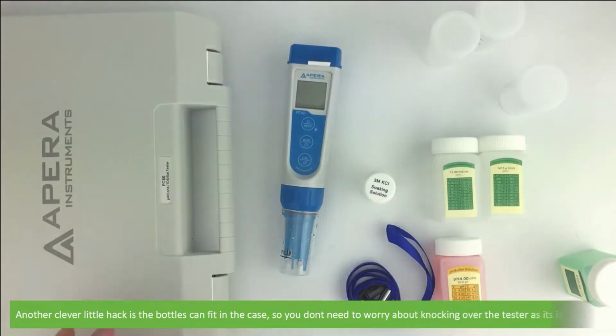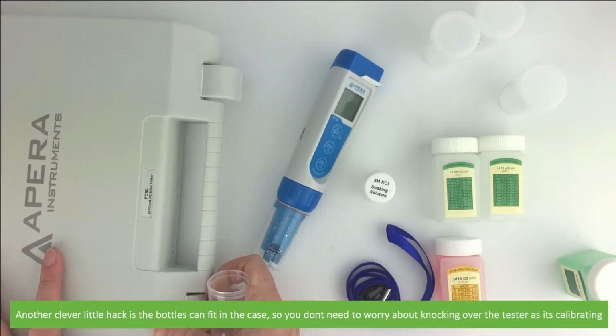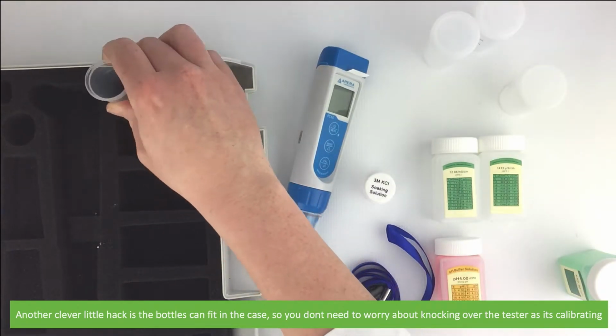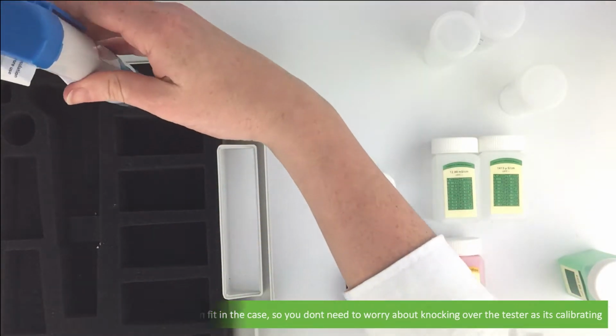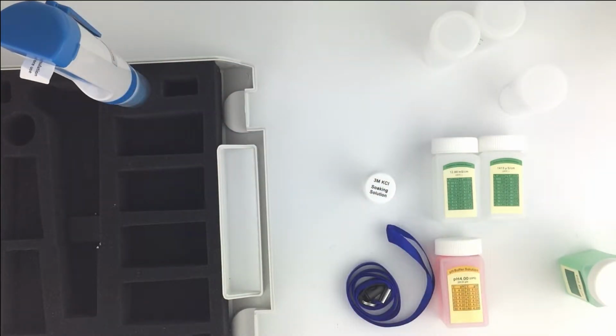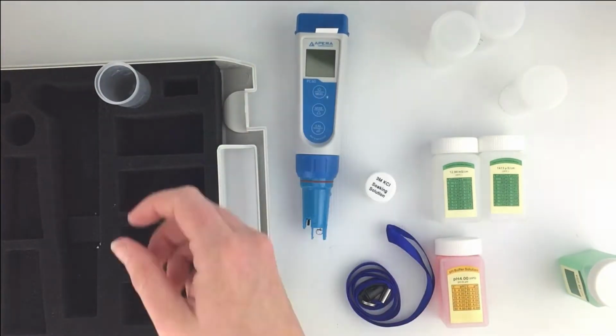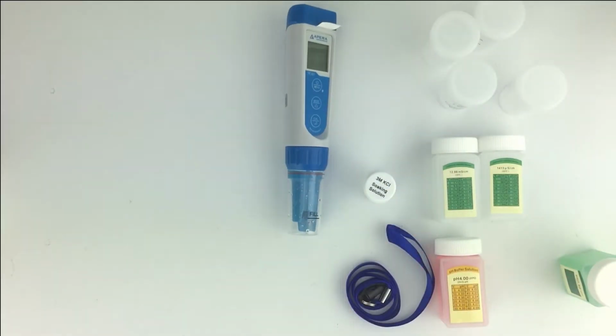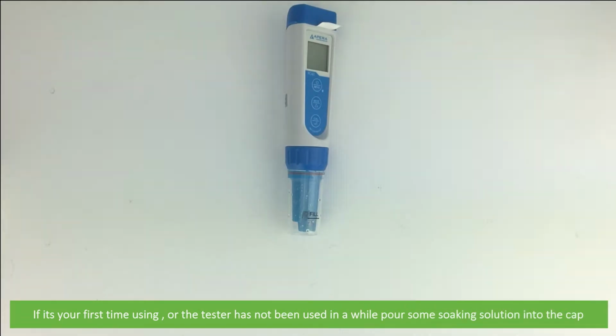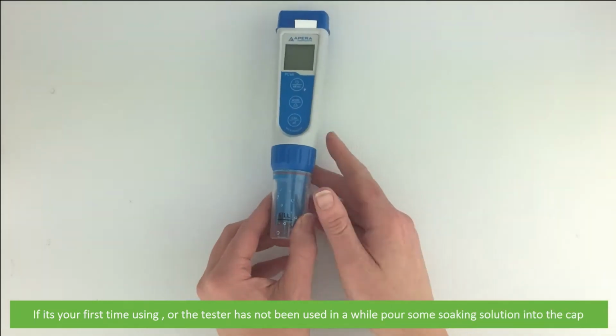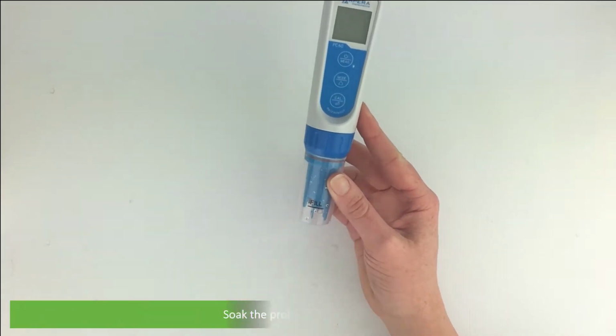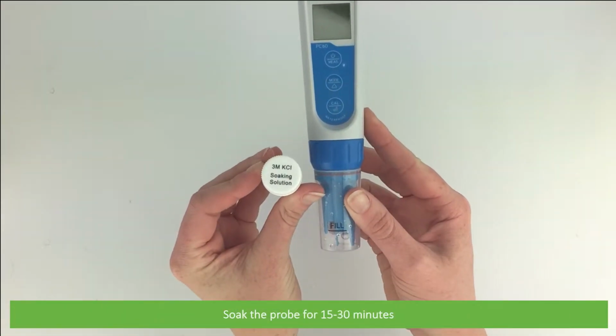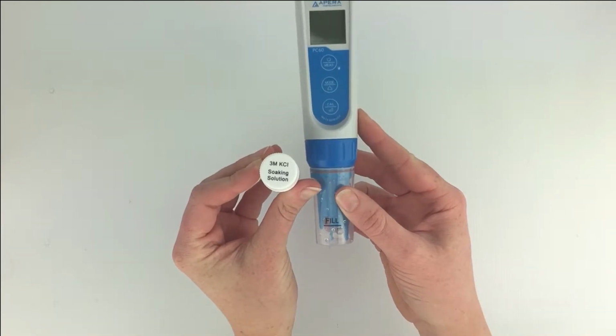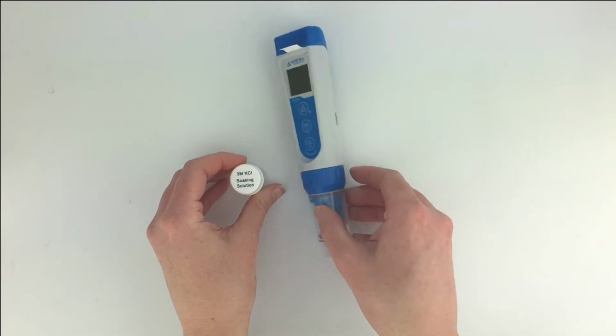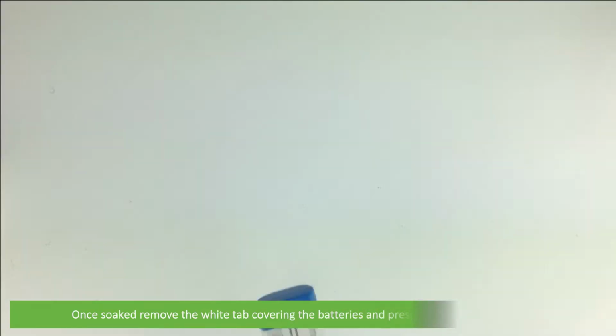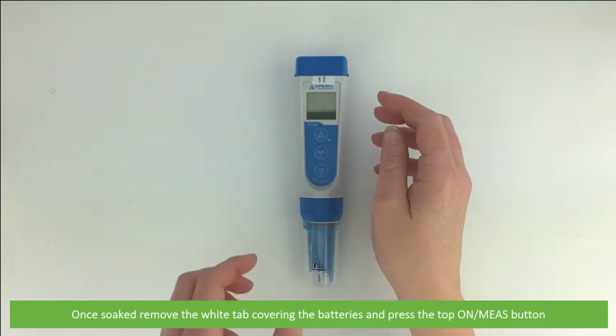Another clever little hack is the bottles fit in the case, so you don't need to worry about knocking over the tester as it's calibrating. If it's your first time using or the tester has not been used in a while, pour some soaking solution into the cap. You should soak the probe for 15 to 30 minutes. Once soaked, remove the white tab covering the batteries and press the on/measurement button.